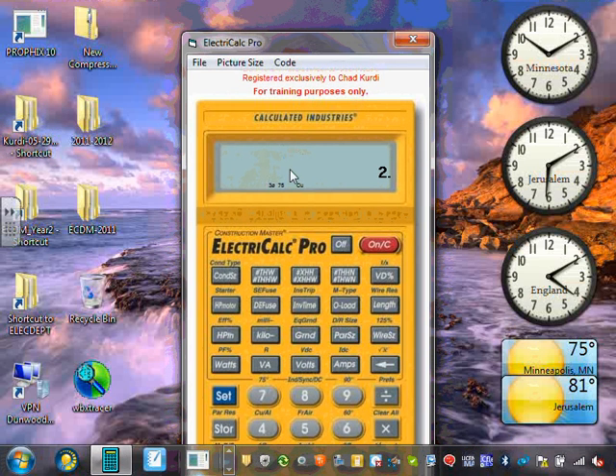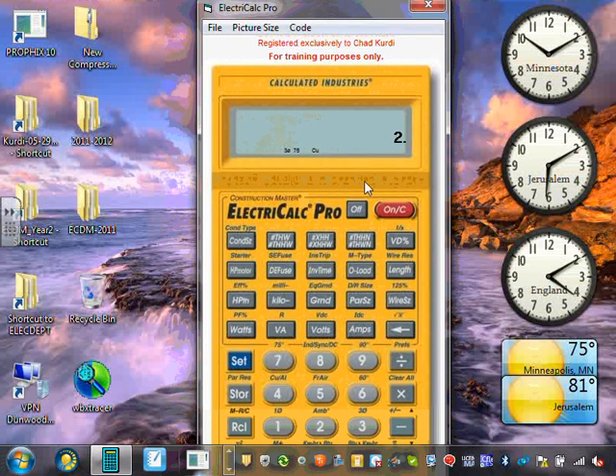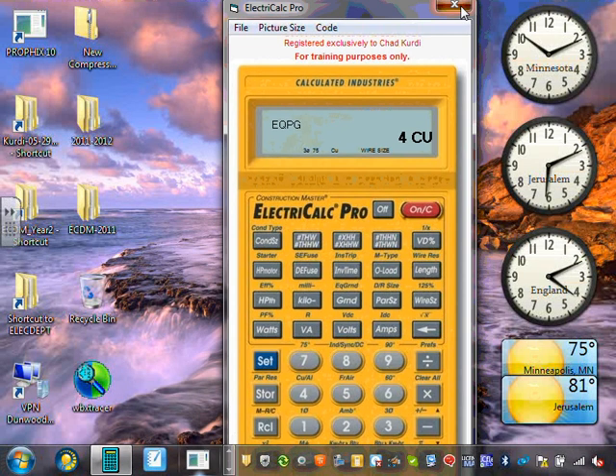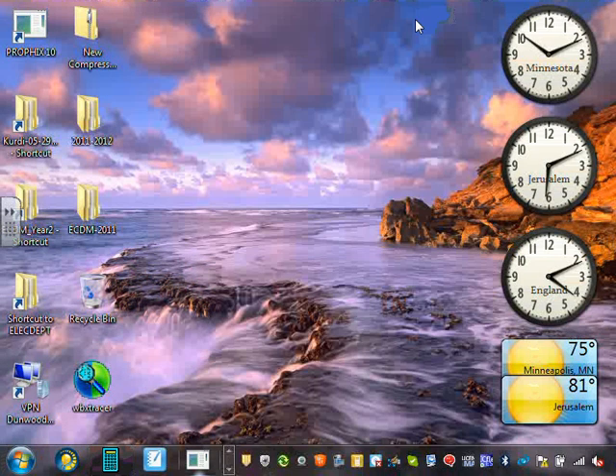Anyway, can you guys size it? Let's just say 200, and I don't have a zero, so 225 amps. Can you guys see? Here's a 225 amp set, and the ground here is number 4 copper. That's how we size the equipment grounding conductor for this one. I'm going to close it, but that's really easy if you can see the zero. Let's go back into my equivalent conductor here.